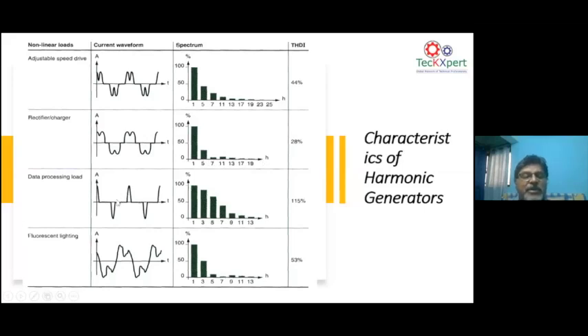Similarly, if you take a computer, the wave shape is like pulses because, as I told you, whenever a voltage is applied to a diode, it conducts only at the peak of the voltage. So you will have pulses of current. When you split this current by Fourier transformation, you have 3, 5, 7 and so on. With fluorescent lighting, the light has to hit a high voltage to start, and then in running mode the voltage comes down. So if you measure the input side of the lighting, you will have a different wave shape, as shown at the bottom.